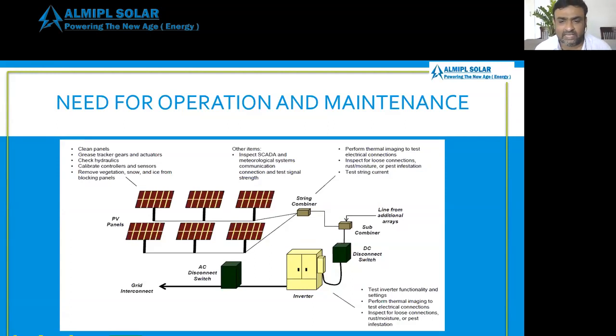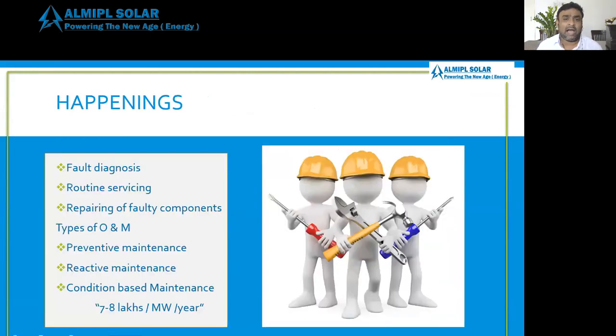Test inverter functionality and settings. Perform thermal imaging to test electrical connections. Inspect for loose connections. So these are the things we need to maintain properly. So when a fault happens, what are the things that regularly happen? So fault diagnostics: if any fault has happened, we need to diagnose it. Routine services, we need to do the routine services, repairing of faulty components. Whatever faulty components there are, inverter or panel or any AC/DC boxes, we need to be prepared.